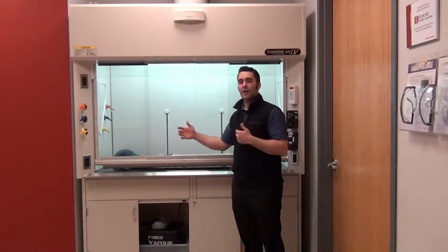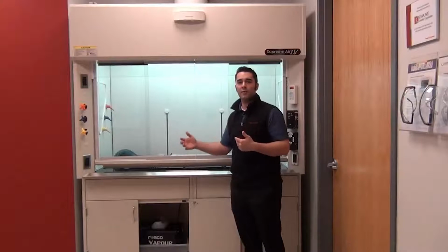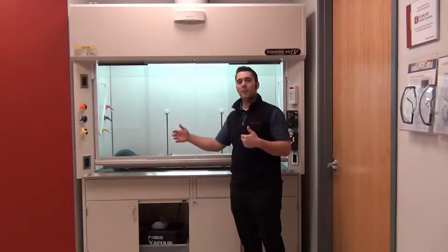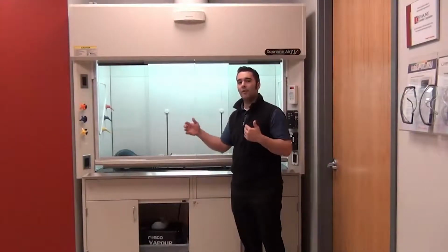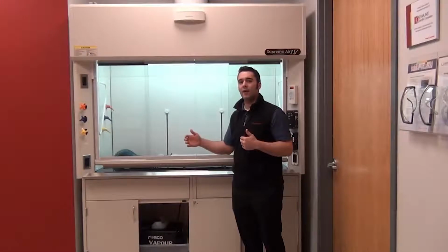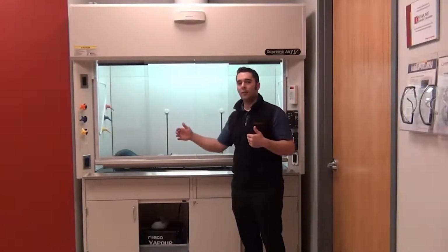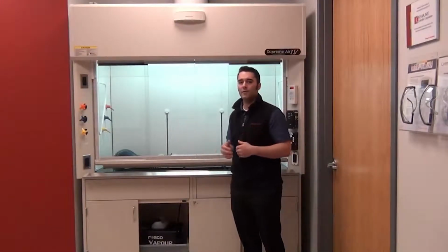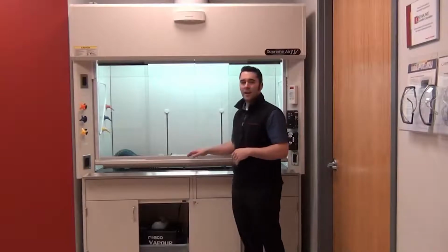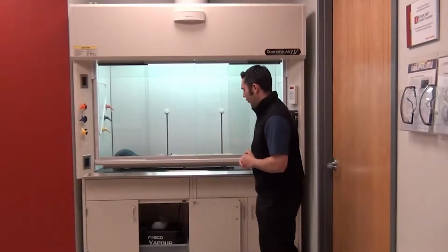So across the entire flow range, or what we like to call the turndown, the minimum and the maximum airflow on the valve, we guarantee plus or minus 5% of accuracy across the entire airflow range within our pressure requirements for the valve. So that's kind of how the valve works a little bit.